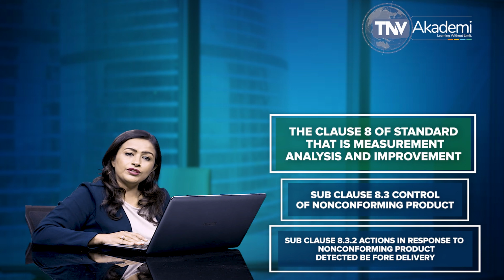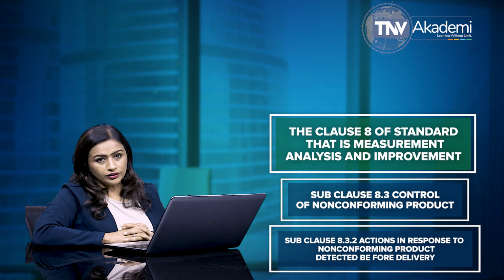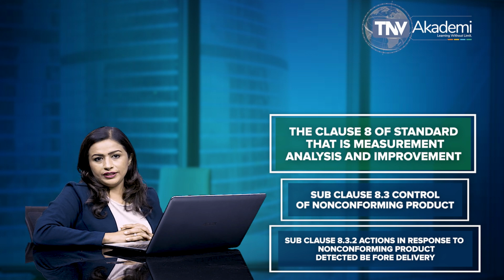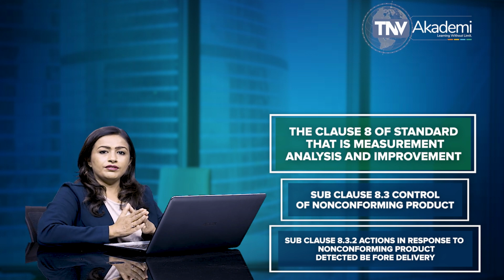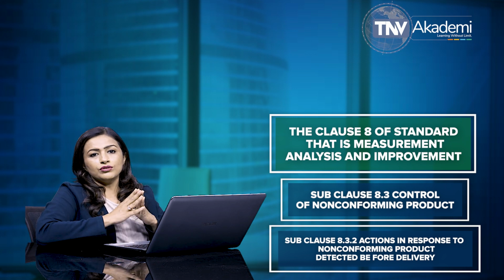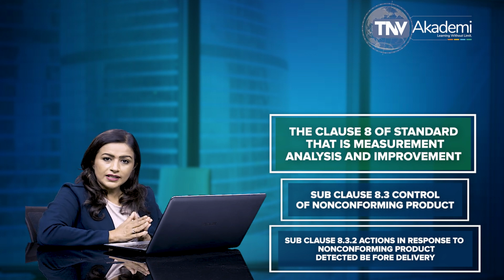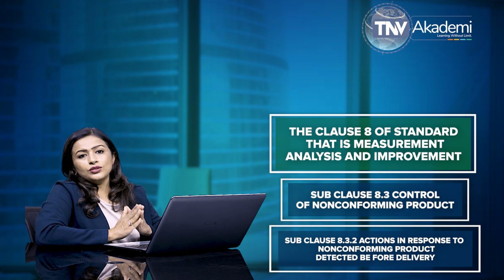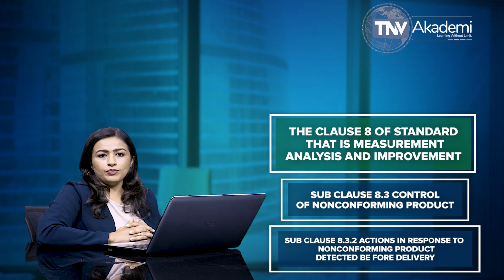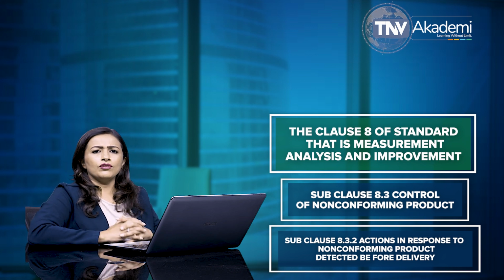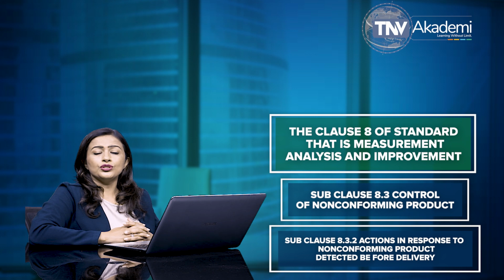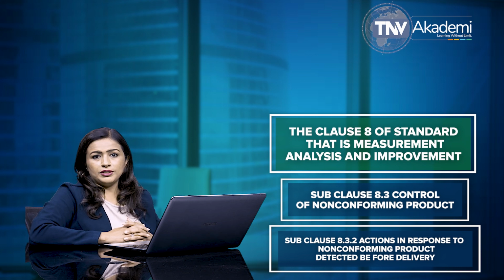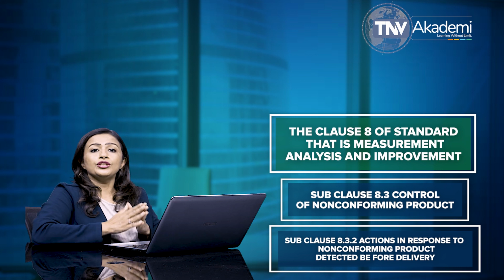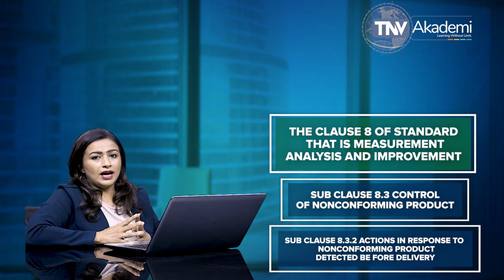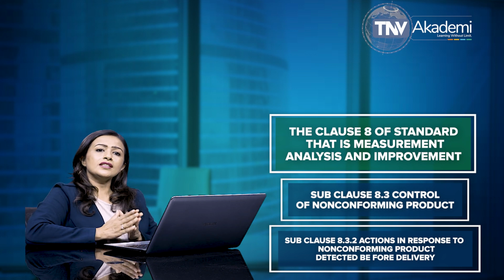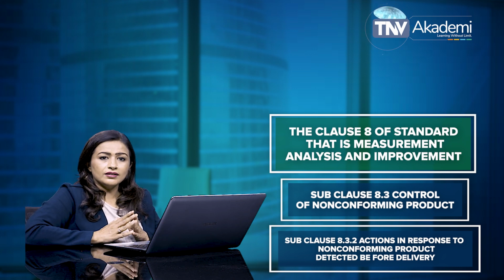Coming to subclause 8.3.2, actions in response to non-conforming product detected before delivery. This subclause 8.3.2 of ISO 13485 2016 states that the organization is required to deal with non-conforming product by one or more of the ways, like taking action to eliminate the detected non-conformity, taking action to preclude its original intended use or application, and authorizing its use, release, or acceptance under concession.